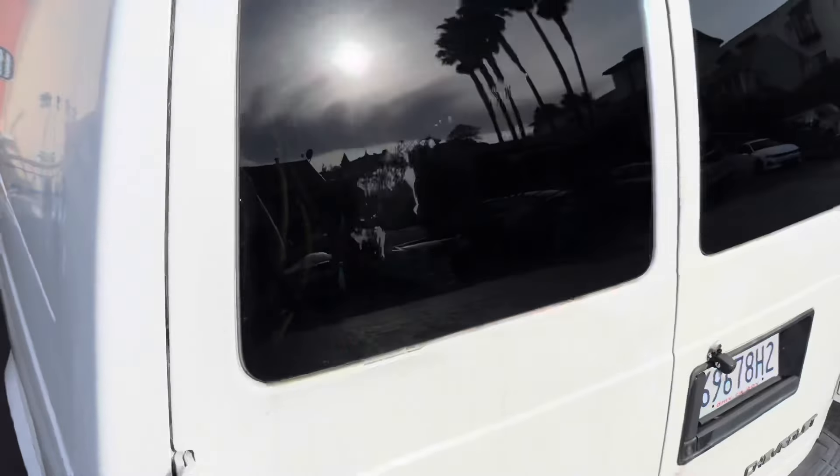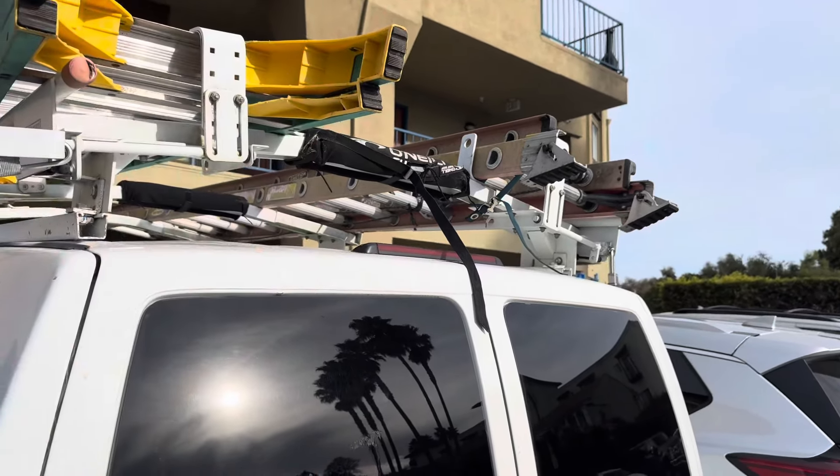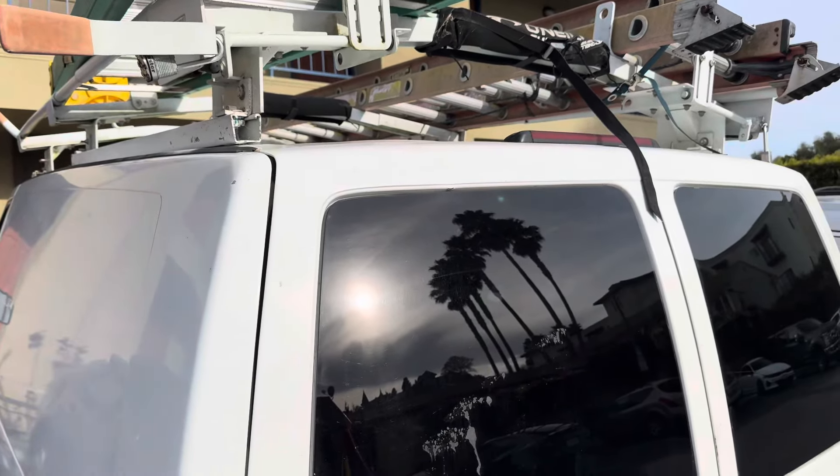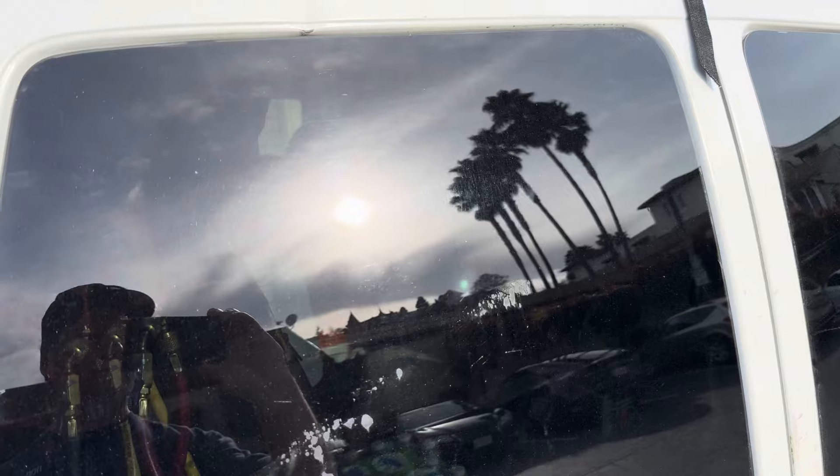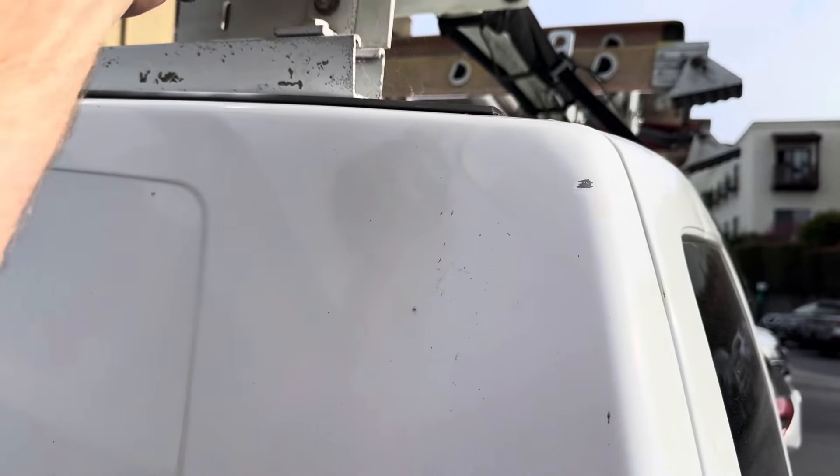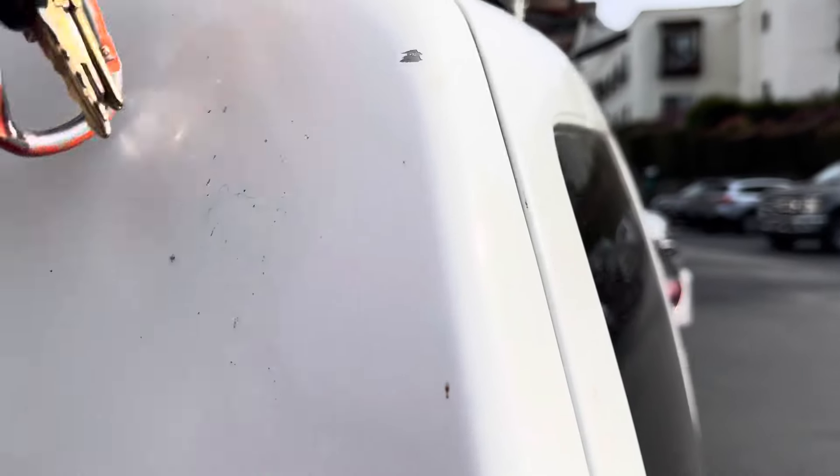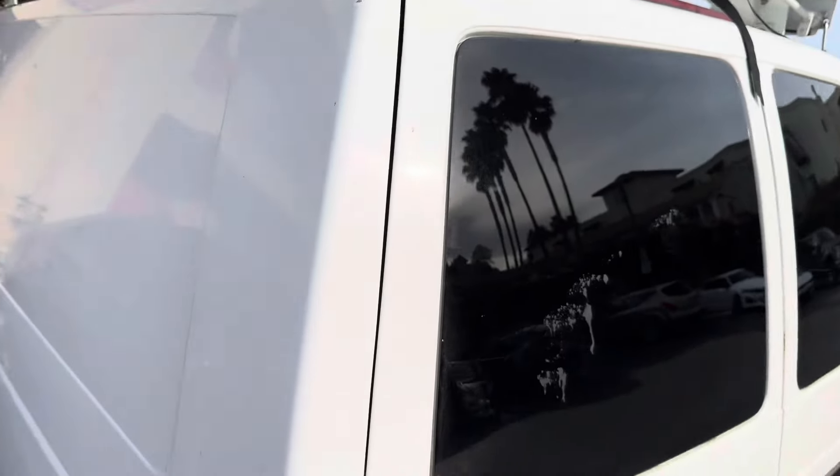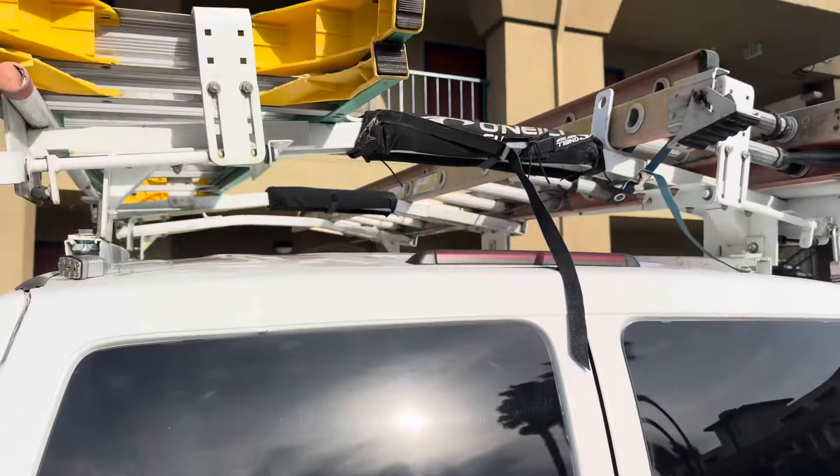I gotta change out this circuit board on an ice maker, a Hoshizaki third floor. Now I didn't order the part, the customer did. They asked me if I'd put it in, I said yes. Third floor at the motel. Look at that cinematic palm trees and sun. There he is, NorCal. Let's get the ladder and Tippins and see if we can get this thing figured out. The issue was the water inlet solenoid was not energizing, so let's see what we come up with.